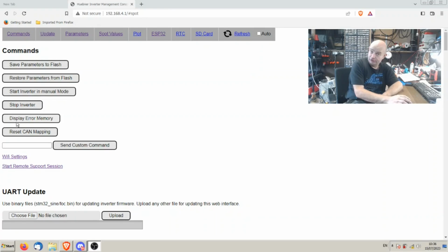Okay, so the next part of the operation is our encoder test. Want to point out that what we have here is 12 volts power applied to the inverter only. We do not have any high voltage, test voltages, contactors, fuses, batteries, or heater elements connected. We don't need them. We're not at that stage yet.